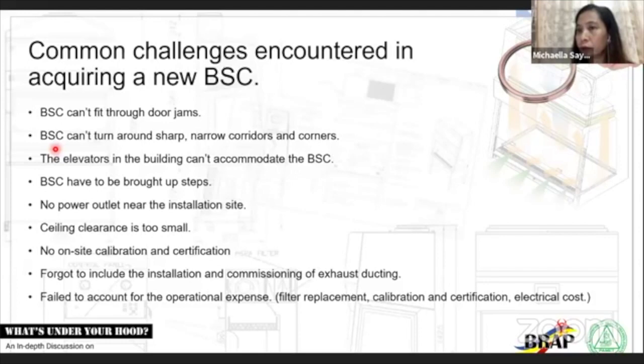Okay. No power outlet near the installation site. People get excited when they buy biosafety cabinets. Parang, oh, dito natin lagay, ha? Oh, maganda yan. This is the appropriate area. You have your clearances. You have your ducting here. It's perfect. Then the biosafety cabinet comes in. Then the supplier would tell you, sir, saan pati sasaksak yan? And you guys would look at yourselves and you'd say, oh my God, we missed that one. Right? Again, the ceiling clearance is too small.